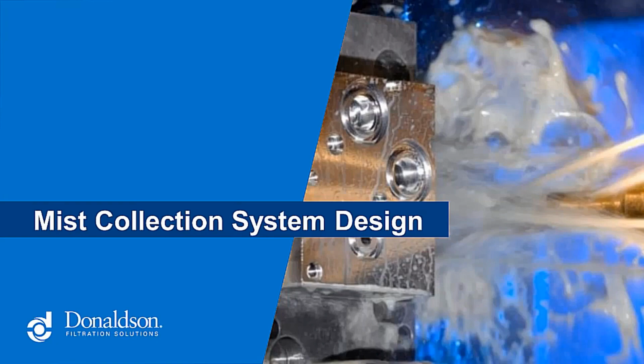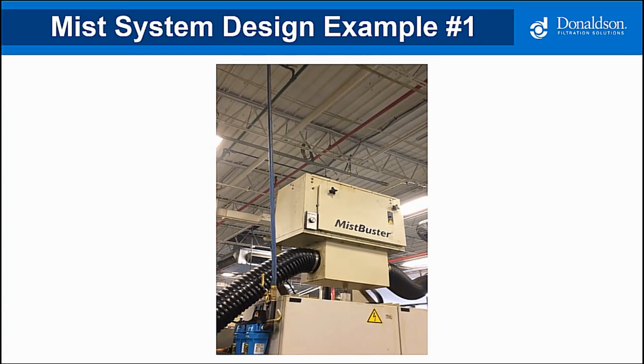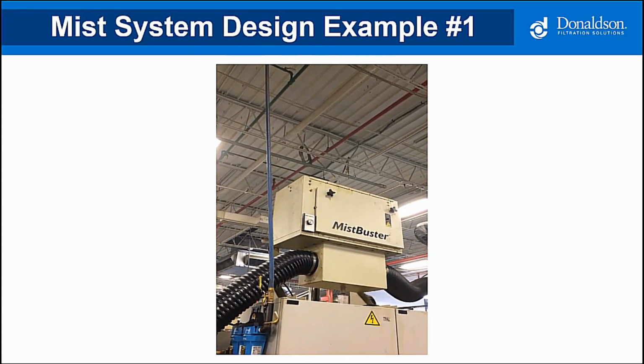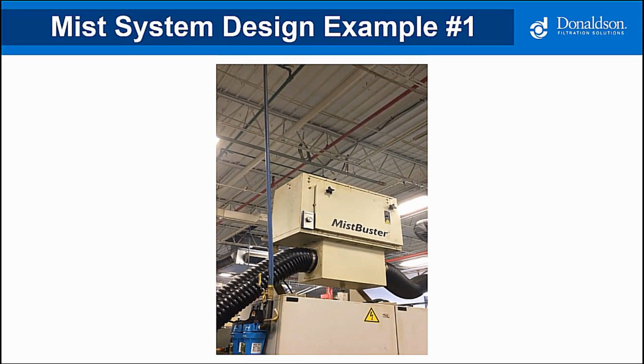Brian, can you get into system design? Yes, thank you, Ashley. So first, I wanted to start off with a few videos of some installations so that you can see the importance of proper mist design. In this particular video, we have an electrostatic precipitator, and hopefully you can see there's a lot of mist and smoke that's bypassing the filtration system.